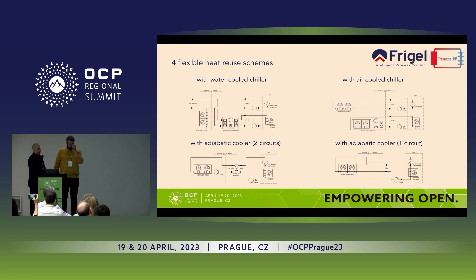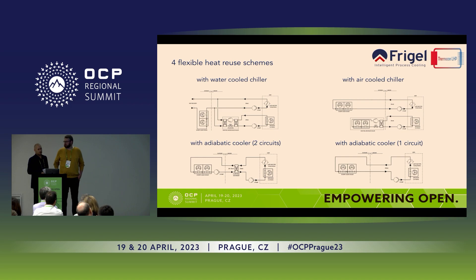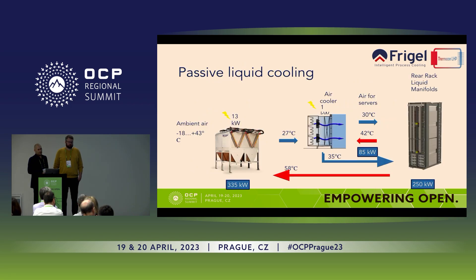There are four solutions shown here. With a chiller, when a customer still wants 20-degree air in the cold aisle, the system can be air-cooled and reuse heat only from the liquid cooling part. If the customer understands that we can shift to adiabatic coolers and eliminate chillers, we can significantly reduce the energy consumption.